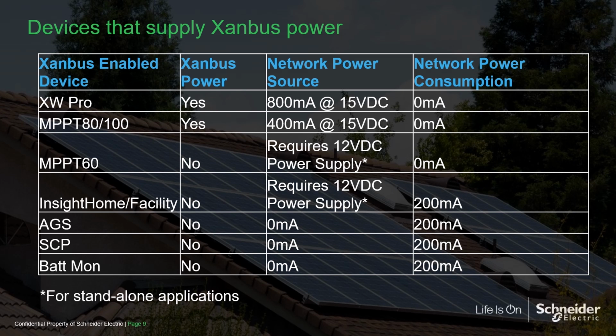Insight Local can be powered by Xanbus. However, Insight Local does not supply Xanbus network power, which is actually supplied by XW Pro and the high voltage MPPT models only. For applications that use MPPT 60 with no inverters, the MPPT 60 aux port can be used to supply Xanbus power. Each MPPT 60 aux port provides 12 volts DC at 150 milliamps.